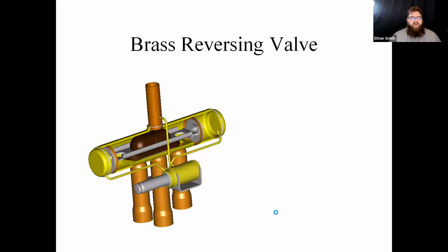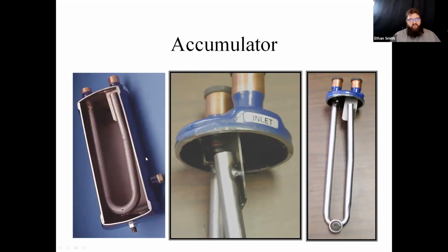As a side note, I just broke down a Mitsubishi unit. It was a big 8-head Mitsubishi unit, and the accumulator can stood almost 4.5 feet tall, because during certain modes of operation that system may have 28 pounds of refrigerant in it. So in the heating mode, if you're only running one head, it's got to put all the refrigerant somewhere. So it goes into these accumulators here, guys.